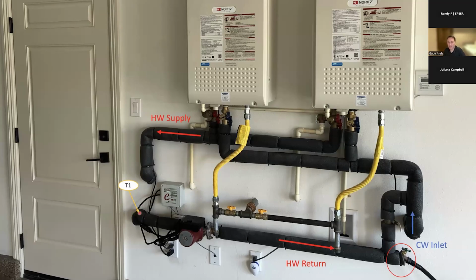Where it says T1 here, this is typically where we have our temperature sensor located. But in an ideal world, you'd want to put that temperature sensor right after the last fixture. If you're able to run that temperature sensor just past the last fixture, that way you're never bringing any hot water back and you're making your system even that much more efficient. But from a practicality standpoint, most often plumbers are just putting that temperature sensor right upstream of the pump where it comes out of the wall. And then finally, you see here on the return line, you have that hose bib, and this is where you can bleed out the air in the line. Very important. And all of our systems and most other Title 24 compliant on-demand systems have a built-in 5-minute timed lockout to prevent airlock.